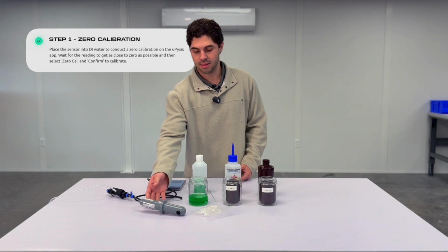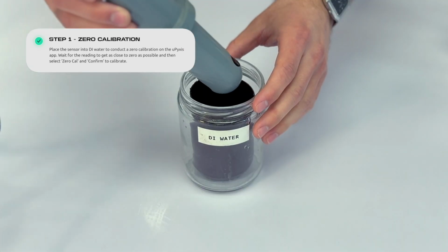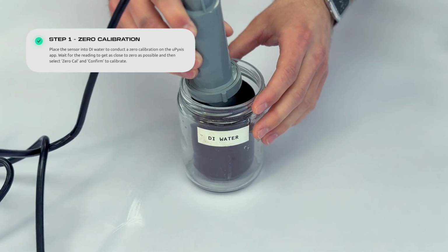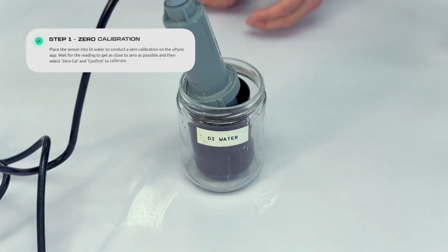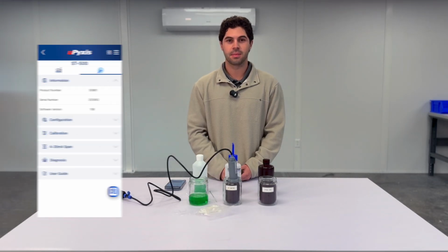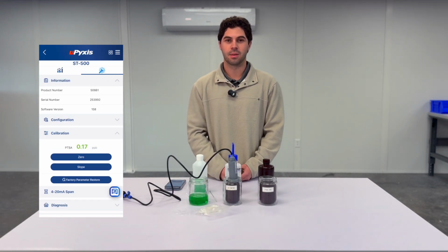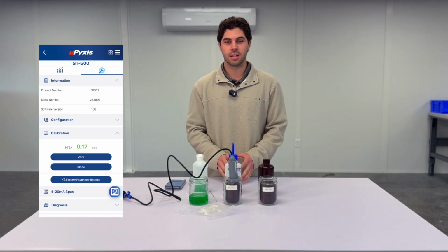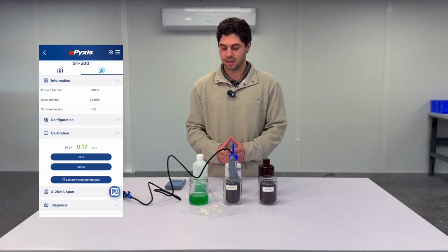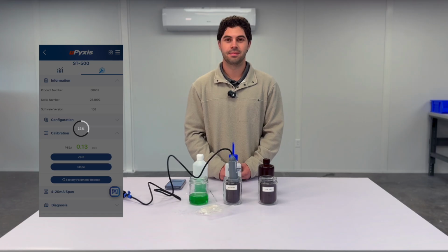So we're going to take the sensor, place it into DI water in the same container that doesn't let in ambient light. Head over to the Pyxis app, go to the Configuration tab, Calibration, let the reading get close to zero as possible, and then hit 0 and confirm.